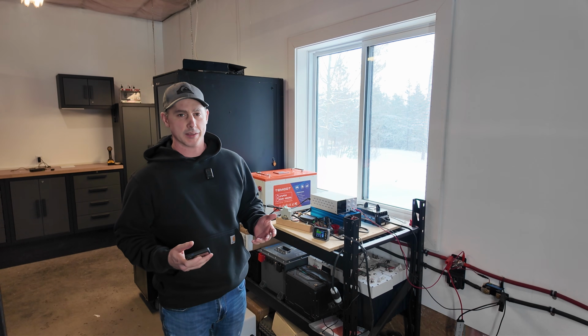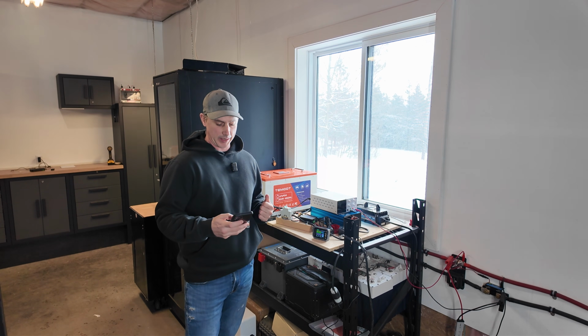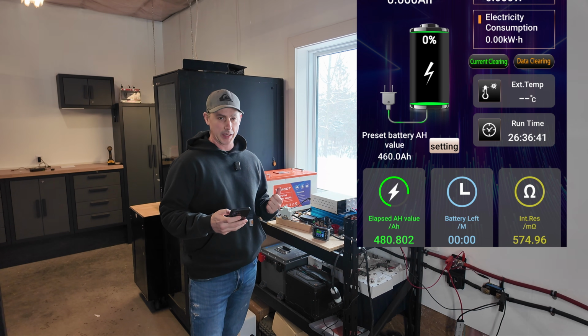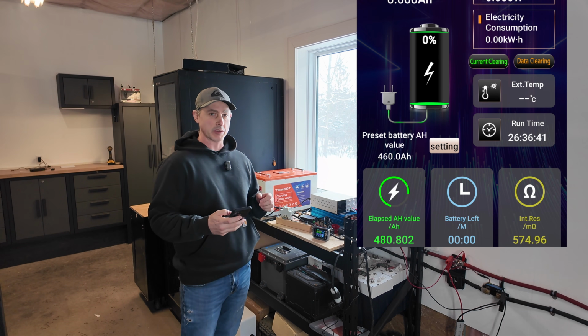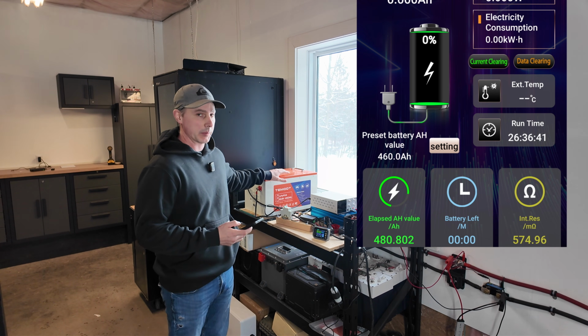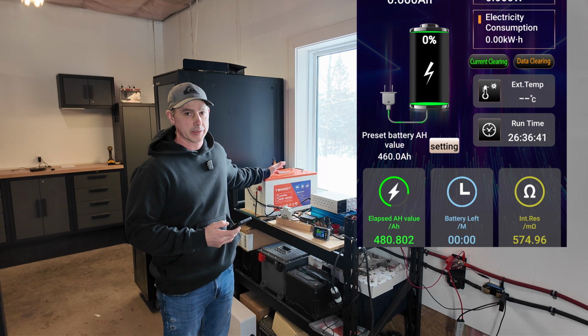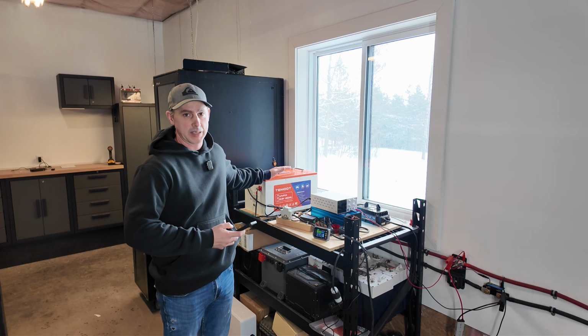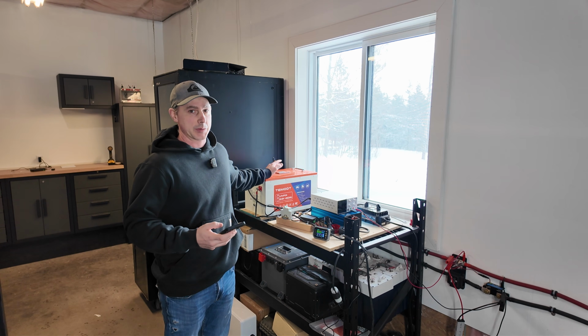All right, my capacity test is done and we tested out at 480.802 amp hours, which is 20 amp hours above the rated capacity of the battery of 460 amp hours. So this test is a pass beyond a pass beyond a pass.